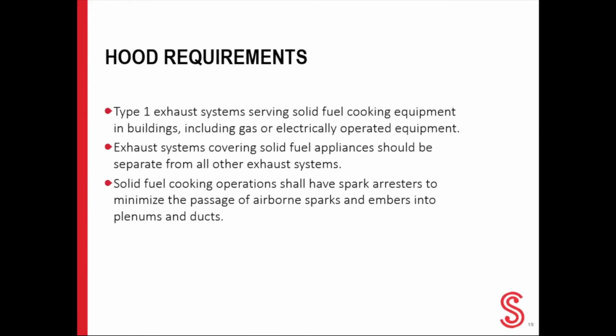Getting into hood requirements for solid fuel. So what type of hood system do you need for a solid fuel cooking operation? Solid fuel units should be covered by a Type 1 hood system equipped with spark arresting baffle filters. For solid fuel cooking operations, their hood should be separate from all other exhaust systems, meaning that the solid fuel unit's hood system should have its own ductwork and exhaust cap. Additionally, the solid fuel unit should be the only cooking appliance under this hood. Solid fuel appliances cannot share a hood system with another cooking appliance.